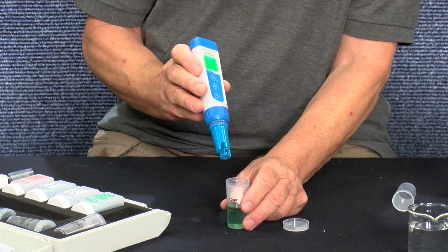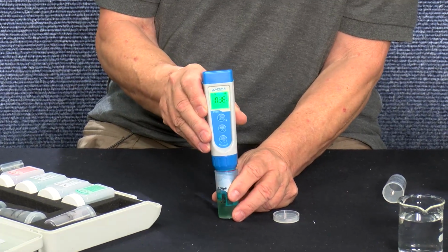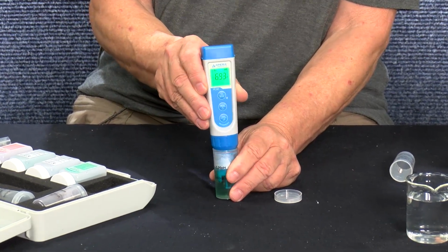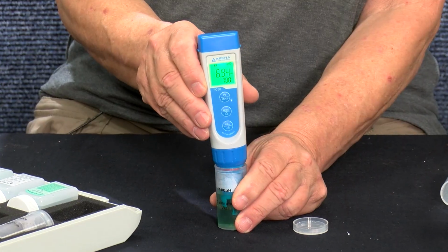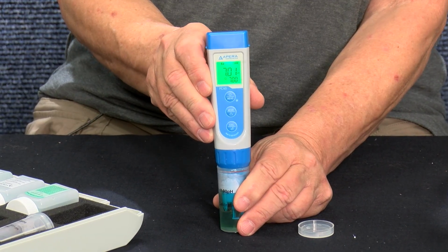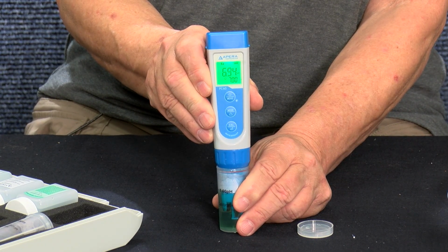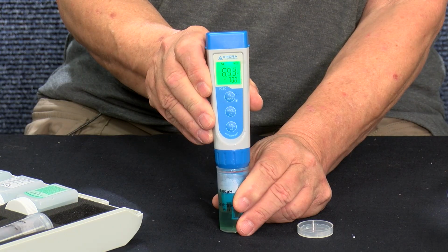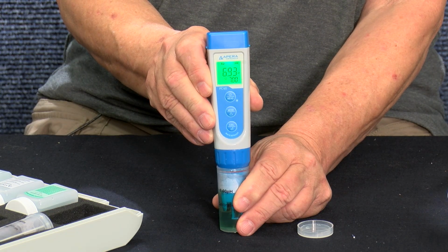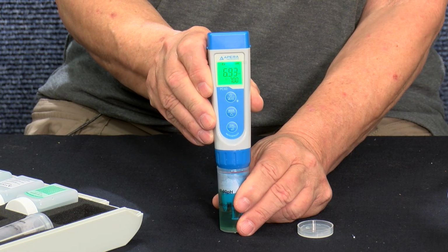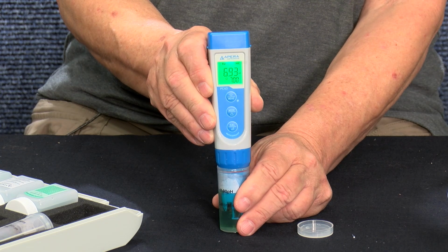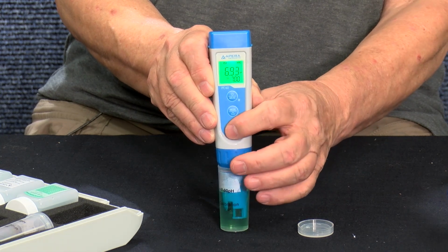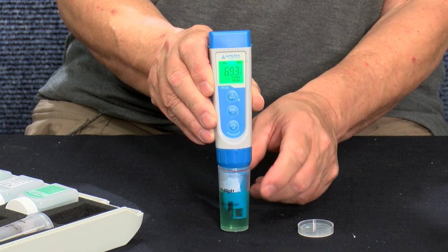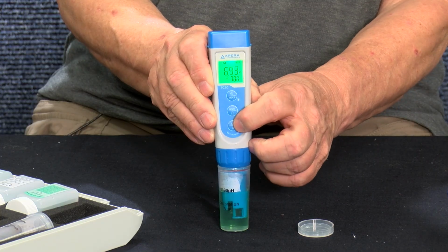Okay, so now we dip the meter into the solution. Make sure the probe is covered, and it's going to give a reading. 6.93. Okay, so the reading now is 6.93. That's what it's reading, but we know that the solution is 7.0.